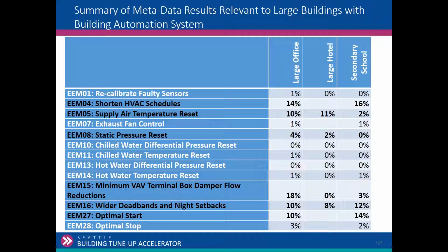Wider dead bands, we talked about that. Optimum start, the same thing. So when you have BAS systems, the opportunities are going to be more on the control side, and specifically on the reset side, whether it's chilled water reset, boiler water reset, fan pressure reset, or supply temperature reset. For those that want to get into the weeds, you can go to PNNL's website and download this report that they did. They modeled out the savings that they found in the field across 100 buildings, so if you want the nitty-gritty details of their findings, it's there.